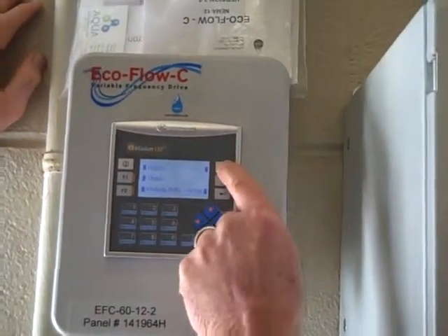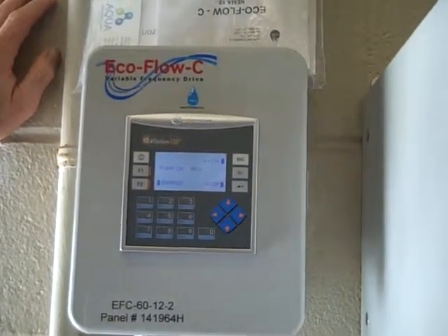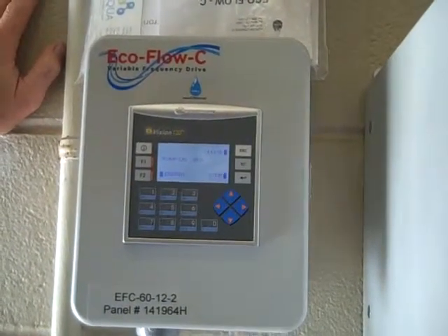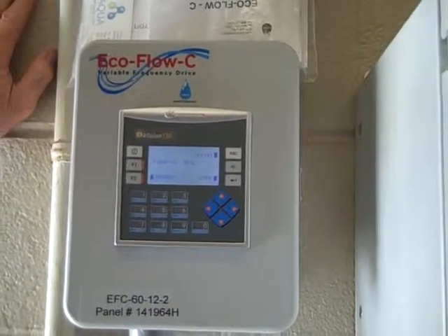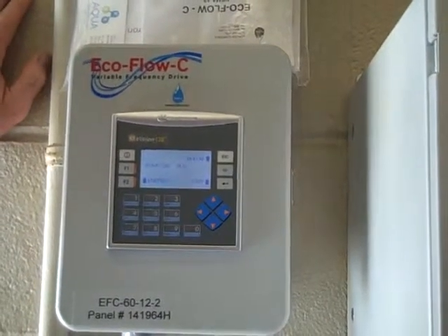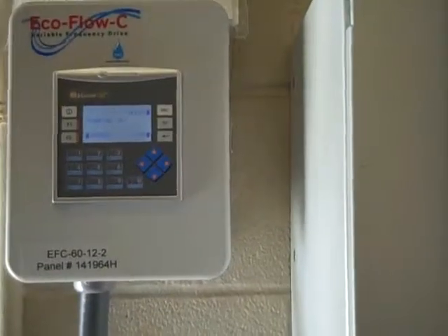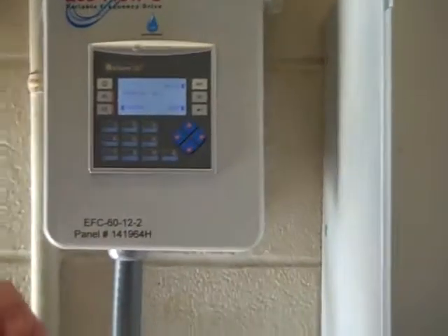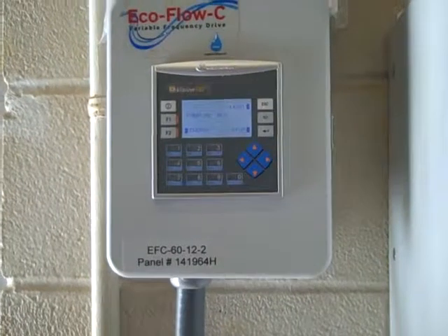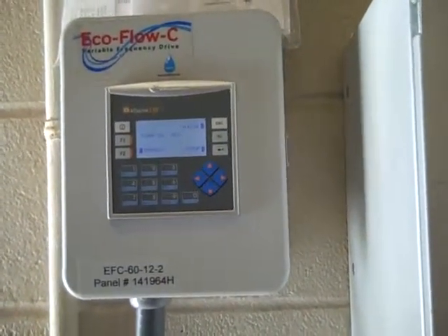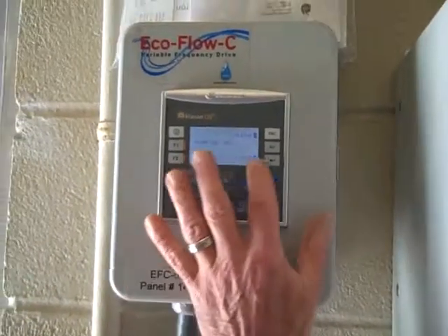I don't know if you remember what the amperage was there. Now we're going to exit and hit auto run. Now we're going to run at 85%, and you'll see the amount of kilowatts in amperage drop. We were at 20, I think, on the amperage. We're 21. See, we dropped down to 19 amps and 8 kilowatts versus the 10 that we were at. So, as you slow it down, it makes a difference. We calculated it, we banked it at 94%, but you can run at 90%, okay? So you'll get a little bit extra savings on it.